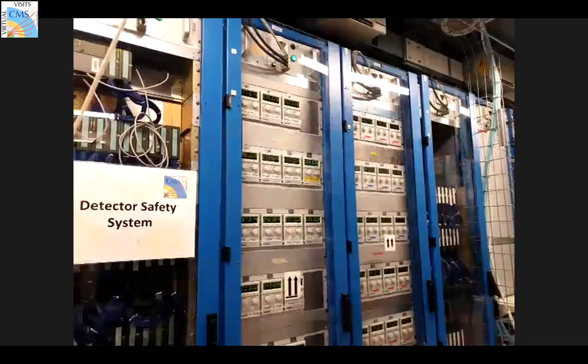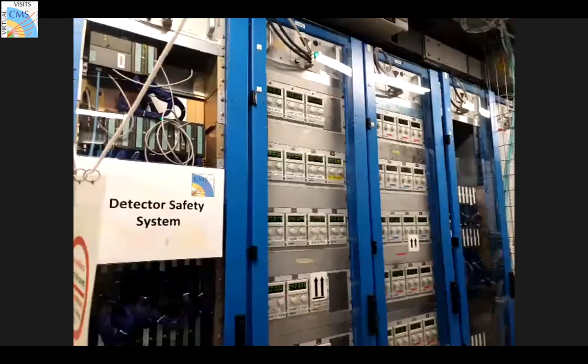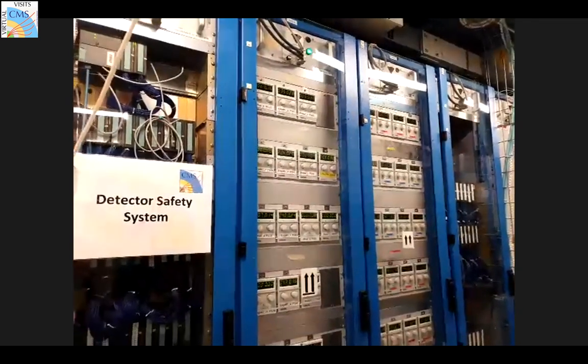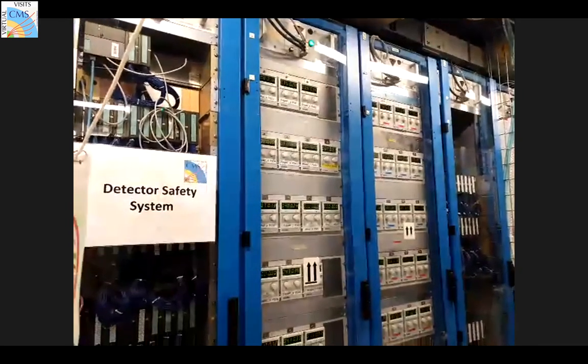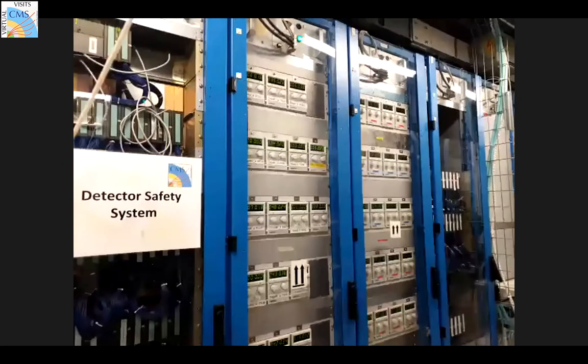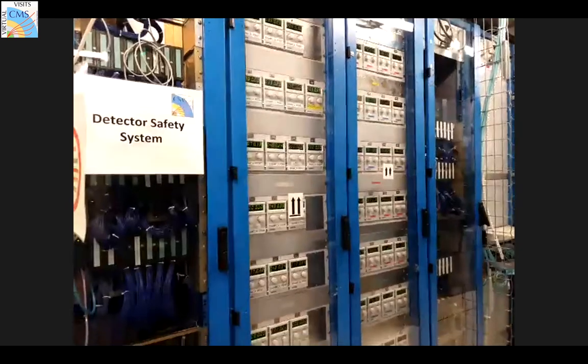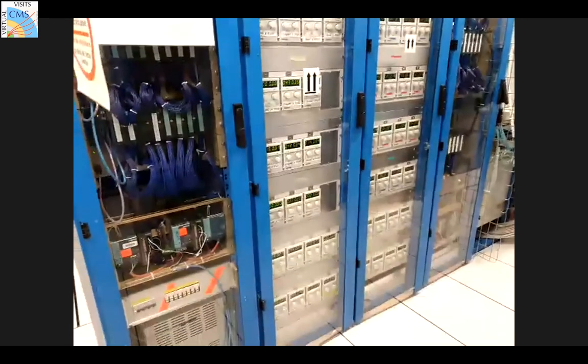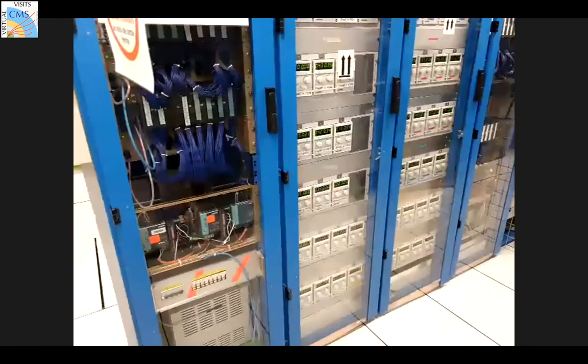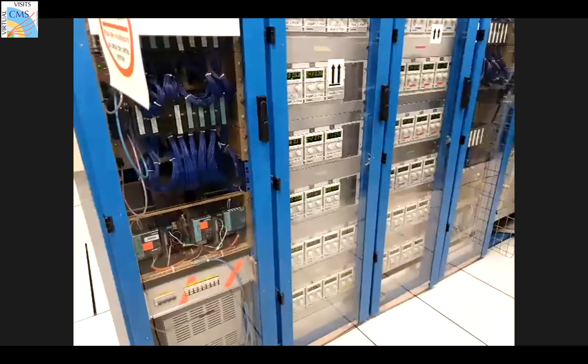But we also have to make sure that on the outside of the detector volume itself, which is well sealed, obviously, because we don't want any humid air to penetrate into it, we're not condensing, because there are other detector systems of CMS in the way. And these power supplies are exactly for the heating elements on the outside of the cold volume, so as to maintain thermal neutrality towards the outside. We always have to be above the dew point. Otherwise, you're condensing like in your bathroom or elsewhere. And that's something that we do not want, because water and electronics never go together well.